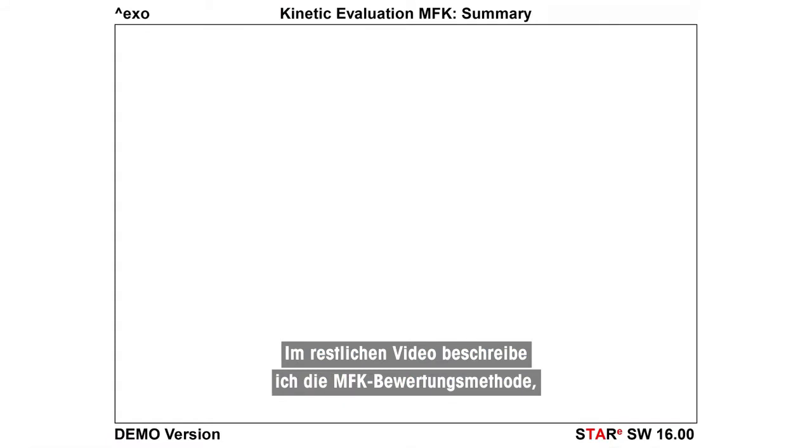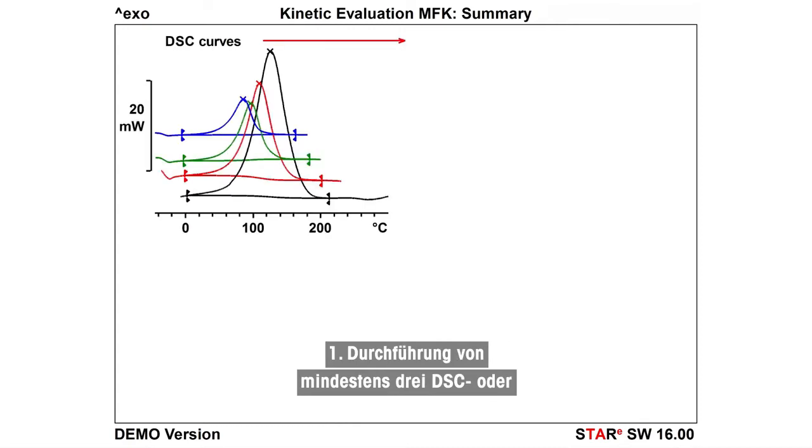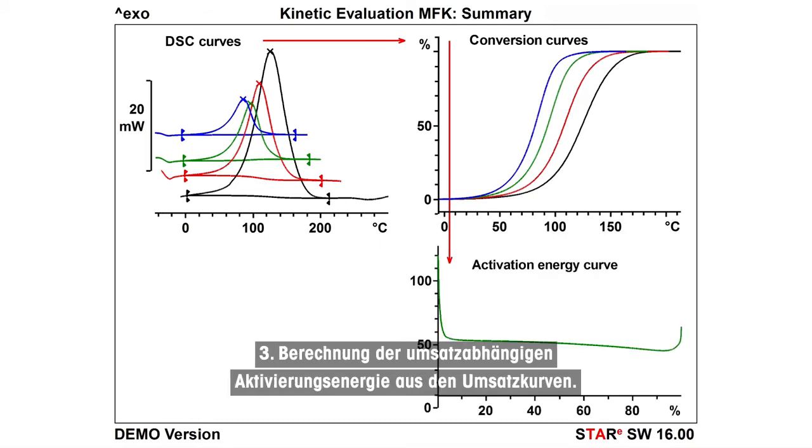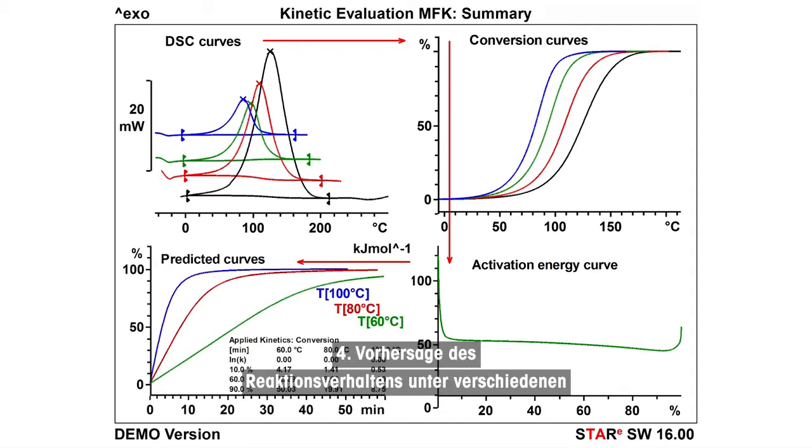In the remainder of this video, I will describe the MFK evaluation method, which can be summarized in four simple steps. 1. Perform at least three DSC or TGA measurements at different heating rates. 2. Calculate conversion curves from the measured curves. 3. Calculate the conversion-dependent activation energy from the conversion curves. 4. Use the calculated activation energy to predict reaction behavior under different conditions.